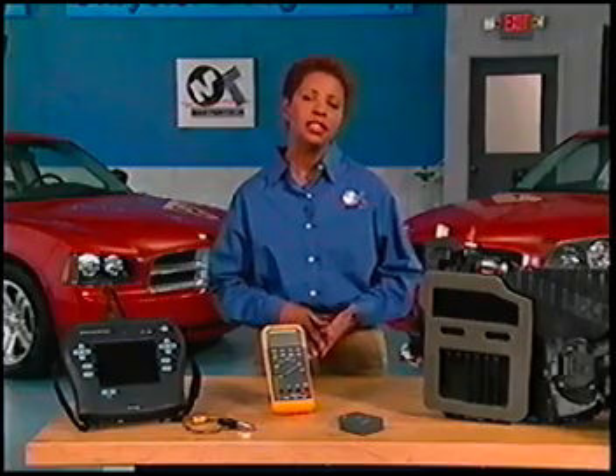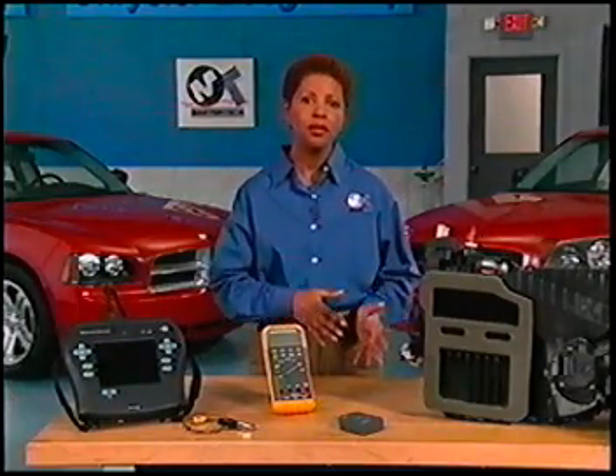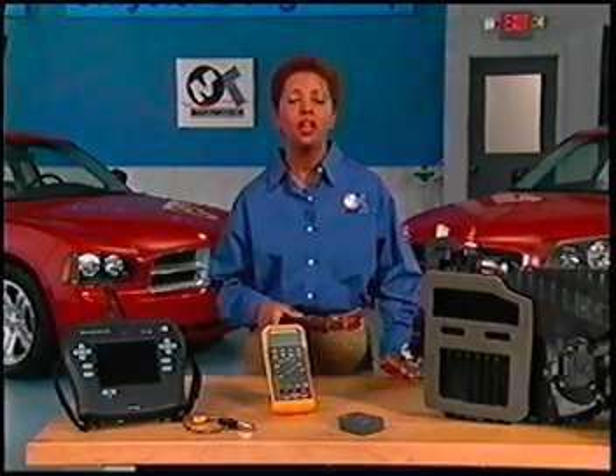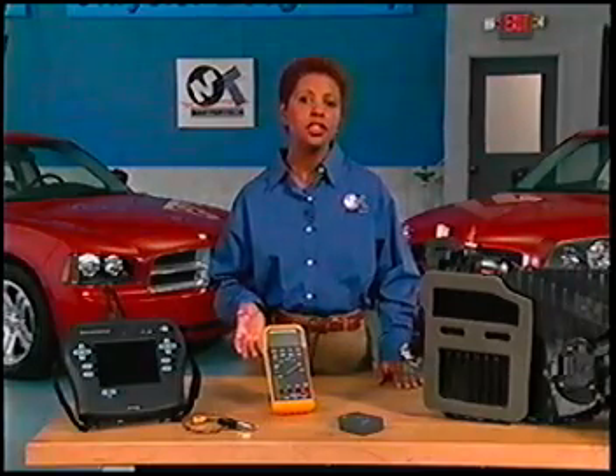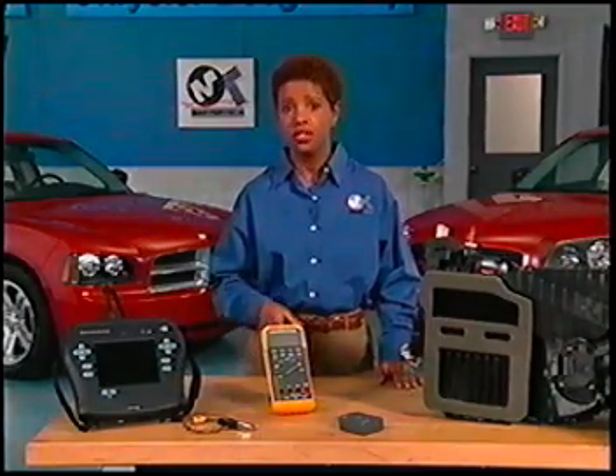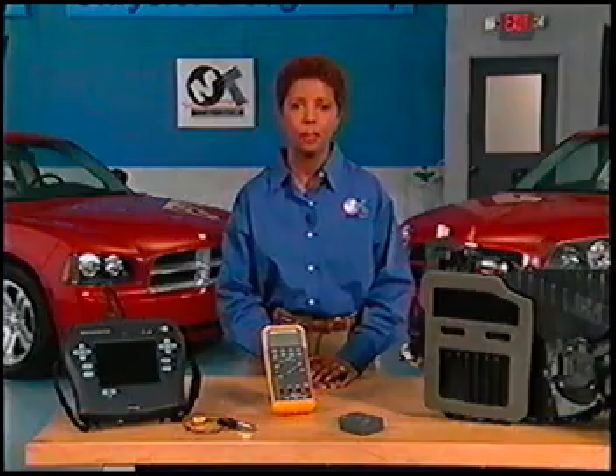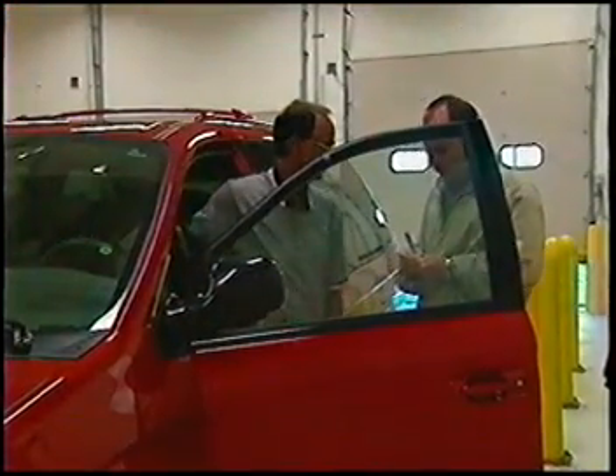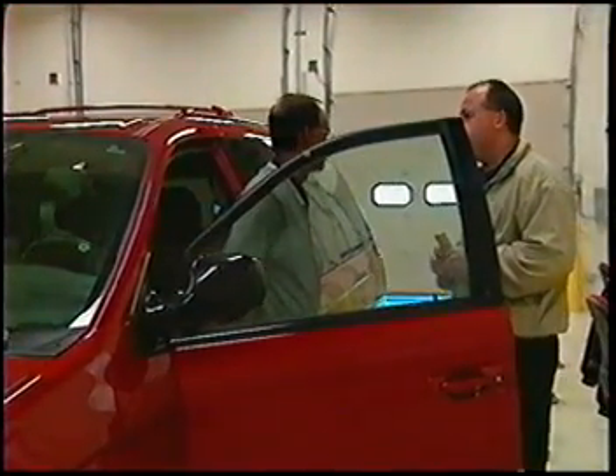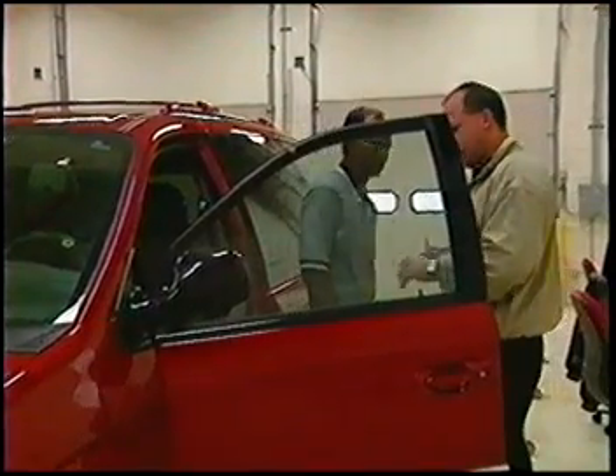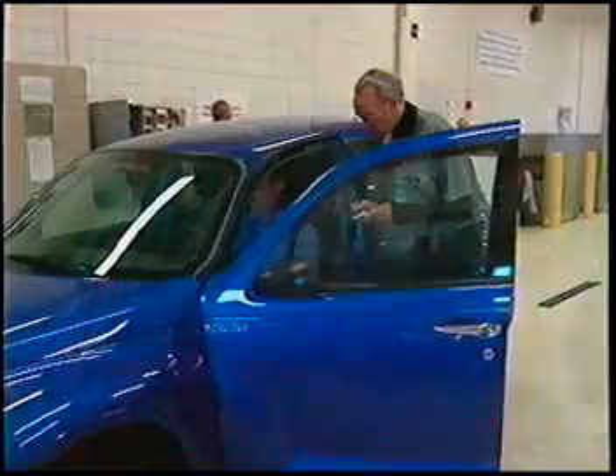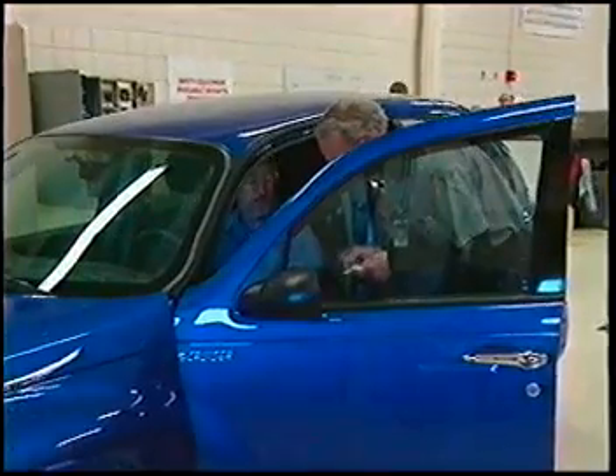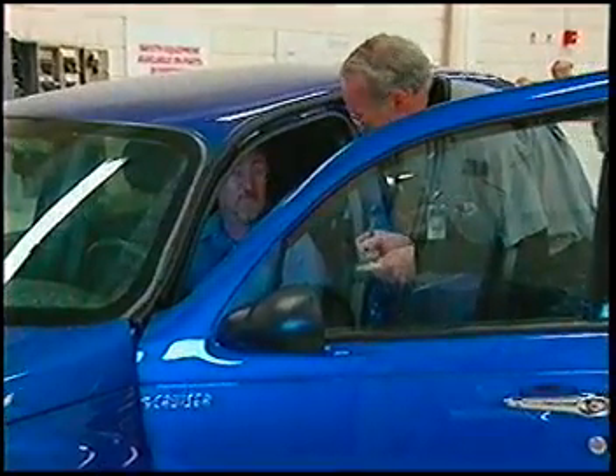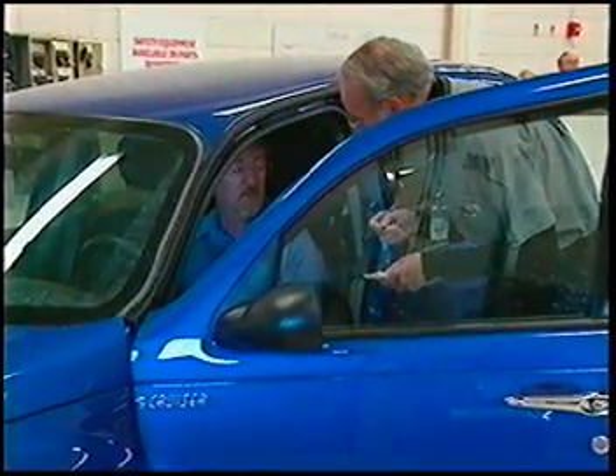The problem with sealant occurs when it enters a recovery recycling machine and clogs passages, and the warranty for most units is void if sealant contamination occurs. To protect your AC equipment, it's a good idea to check with customers to see if system contamination might have occurred, and to use available refrigerant identifiers and sealant detectors to check out suspect systems.